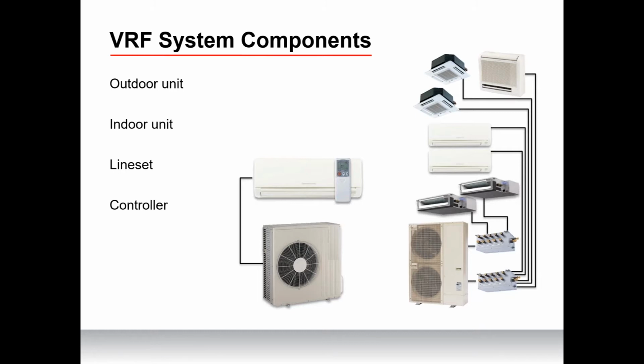The outdoor unit powers the indoor unit, and refrigerant and communication lines connect the two components. The indoor unit can be controlled via handheld controller, wall mount thermostat, or Wi-Fi controller, many different controls options, but there needs to be a controller to actually control that system. A multi-zone VRF system, which we can see over here on the right-hand side of the screen, has an outdoor unit that can connect to multiple different indoor units. The outdoor unit powers each individual indoor unit, and refrigerant and communication lines connect all of the components.